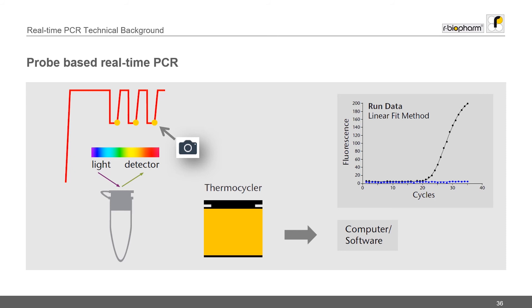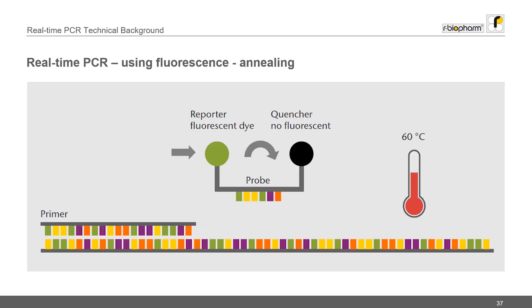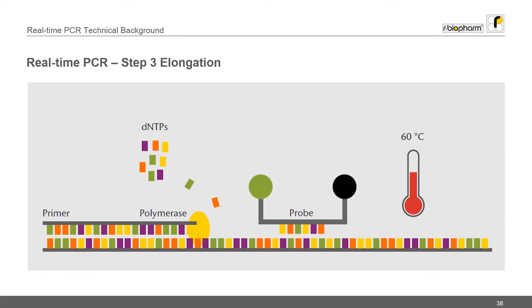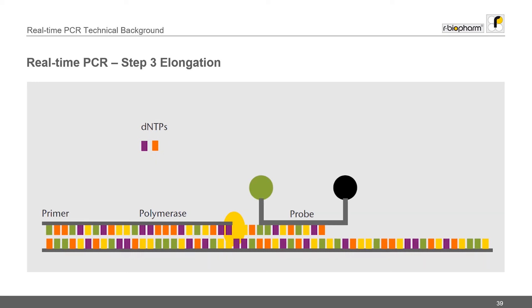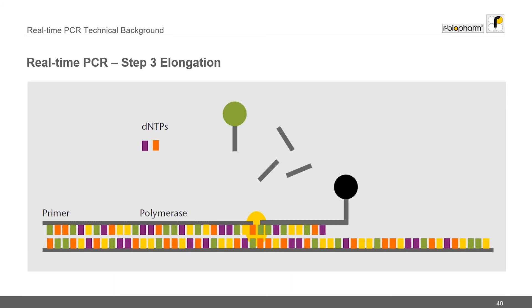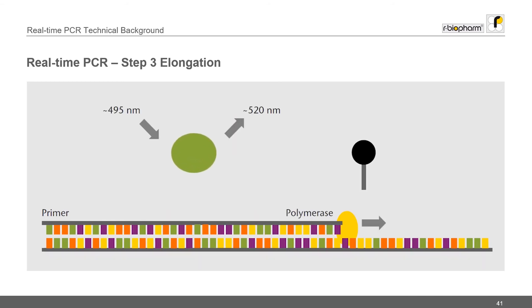As the number of copies increases during the reaction, so does the fluorescence. At rBiopharm we use a hydrolysis probe-based detection technology called TaqMan to generate fluorescence during the PCR. The probe consists of a fluorescent reporter and a quencher molecule. These target-specific probes are designed to bind downstream of the primers during the annealing step. As long as the reporter and quencher are physically close to each other, no fluorescence is emitted. The probe is then cleaved by the polymerase enzyme during the elongation step, separating the reporter and quencher, so the quencher no longer suppresses the reporter and the level of fluorescence increases. With every cycle of PCR, more probes are cleaved and more fluorescence is generated.